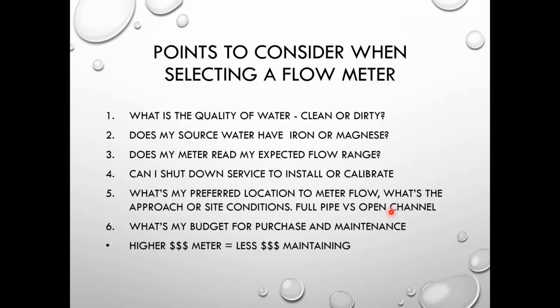What's the preferred location? What's the approach or site conditions? And again, I always ask full pipe versus open channel, right? The only way for them to get a good full pipe out of a facility is to drop their plant effluent into a tank and have it pumped out. And then what's my budget for purchasing and maintenance? And of course, the higher cost you spend up front on flow meters is usually less than maintenance.